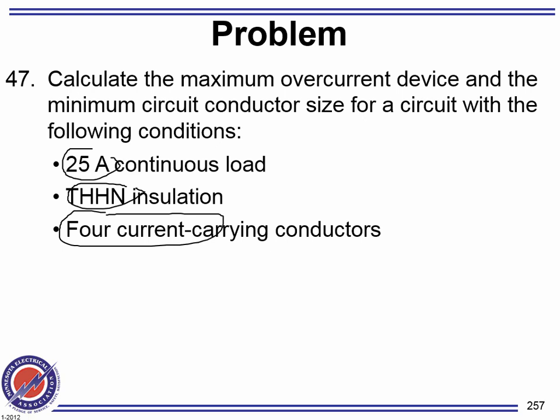It's a 25 amp. We need to find a conductor and a breaker. We need a minimum circuit conductor for that, and an overcurrent protection device, the maximum breaker. The breakers are sized, guys, at 1.25, like for most equipment, 1.25 for continuous equipment.